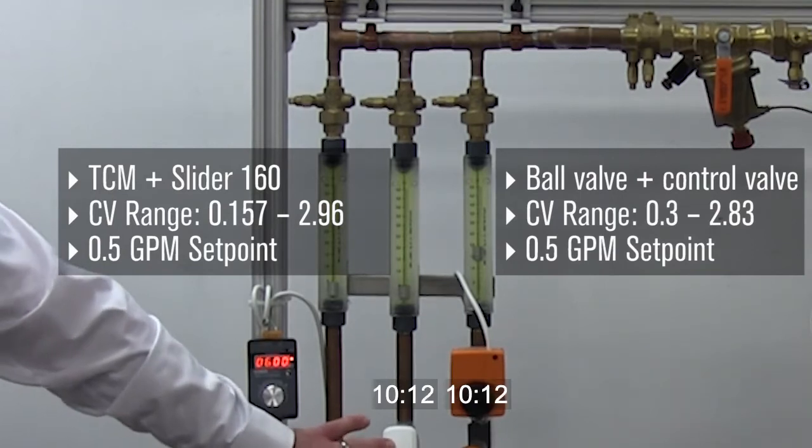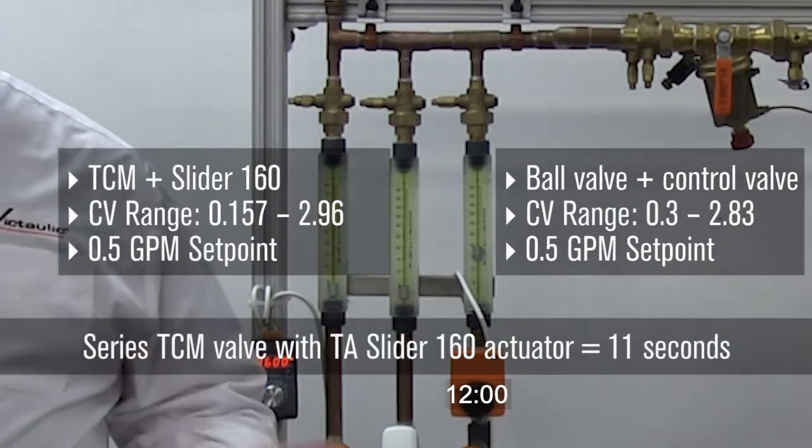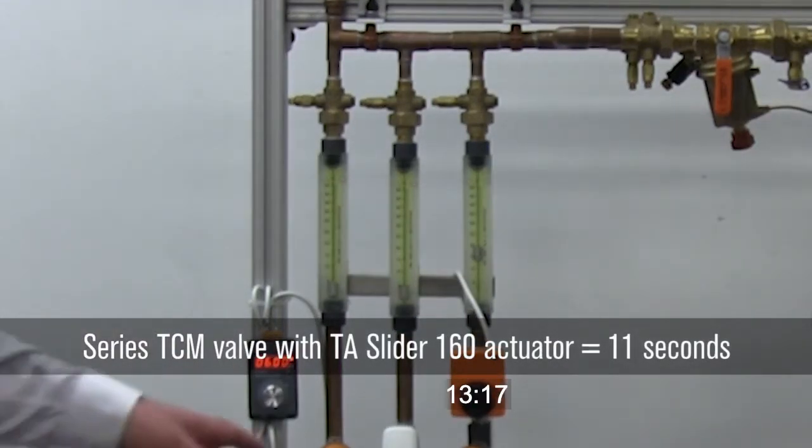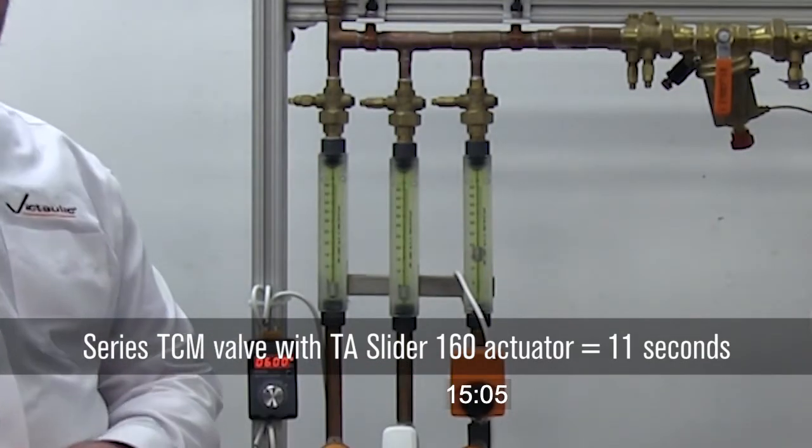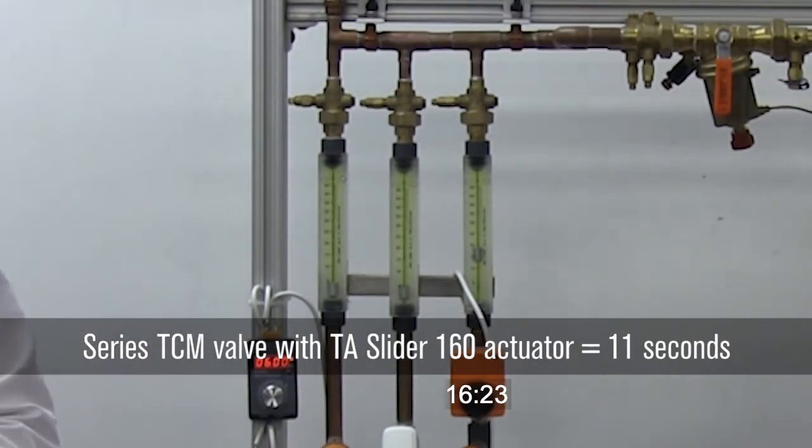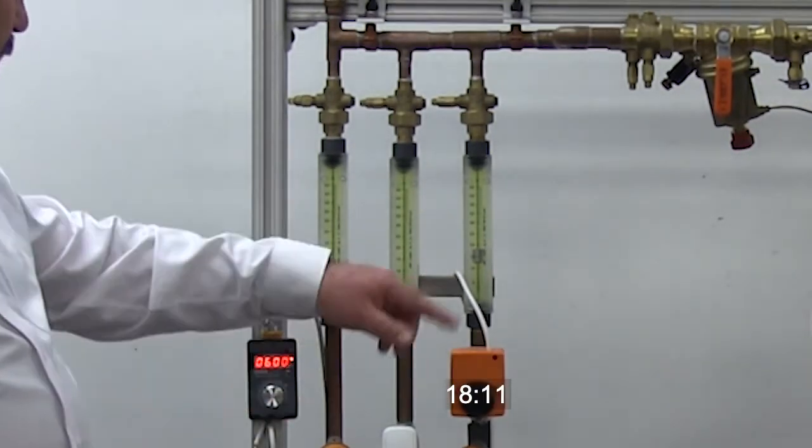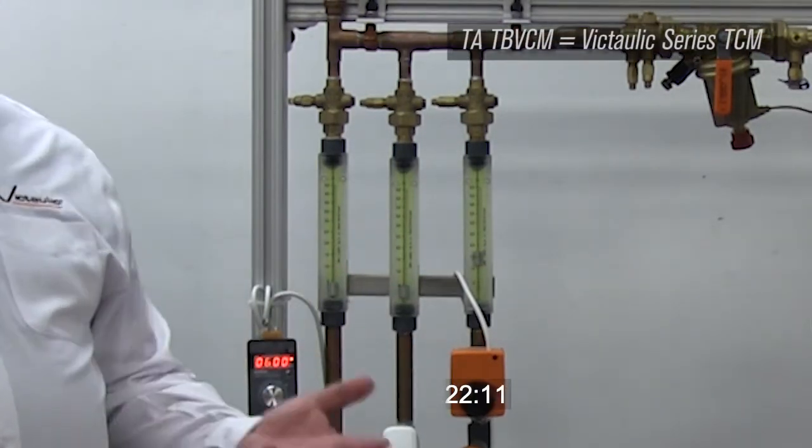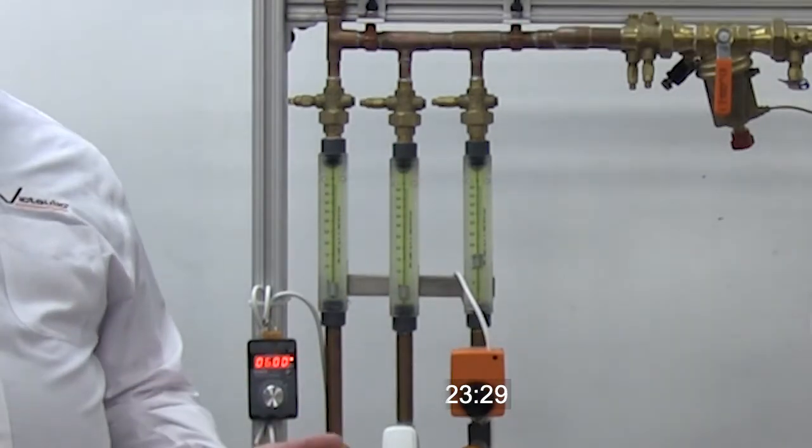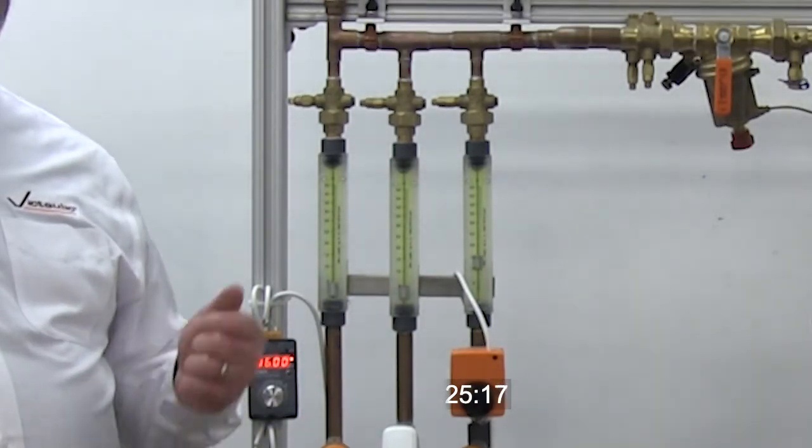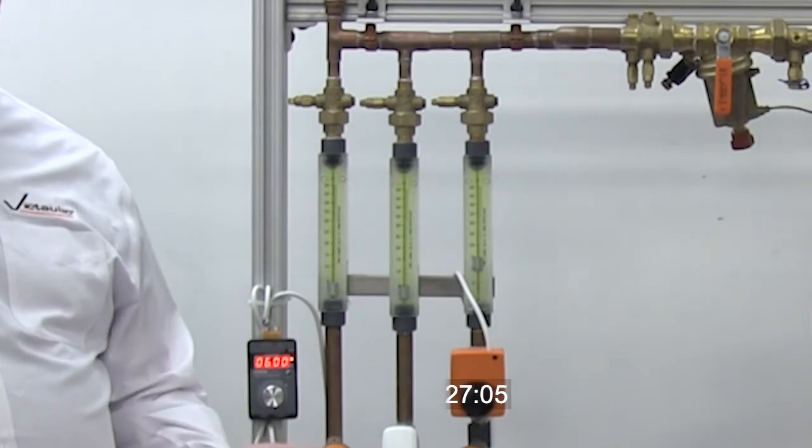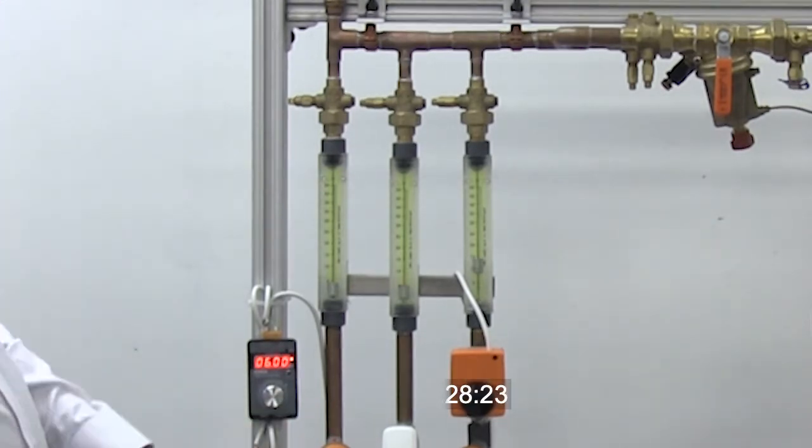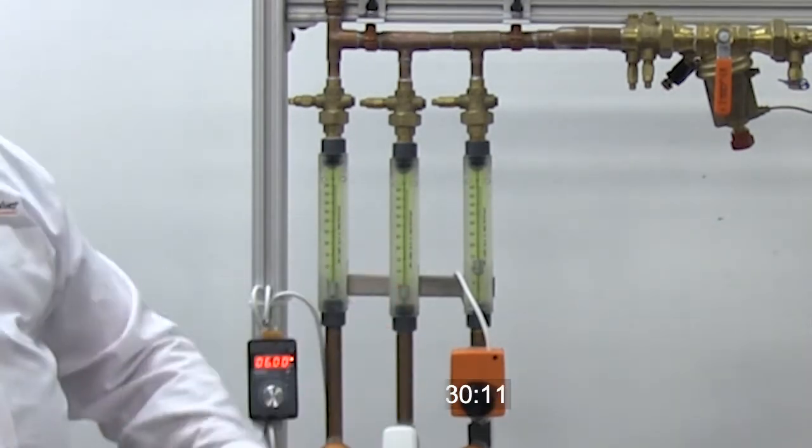Now again, you notice that the Slider gets there very quickly, so quicker control, whereas our quarter turn valve is going to take a little while to get to the point where it needs to be. Now while we're waiting for our quarter turn valve, we'll notice our Slider and our TBVCM has brought us to roughly 20% of the flow rate for the system, so we're right at that 50% heat output for cooling output for the coil. Got there very quickly and it's right where we need it to be.